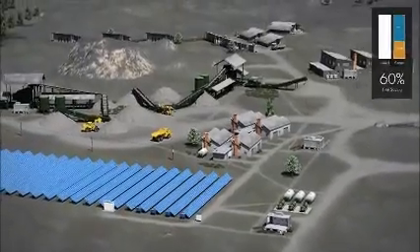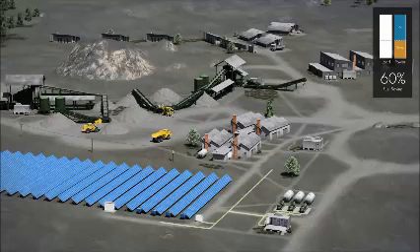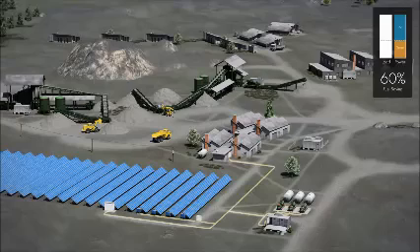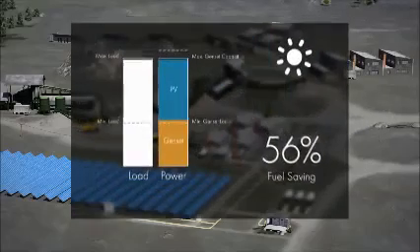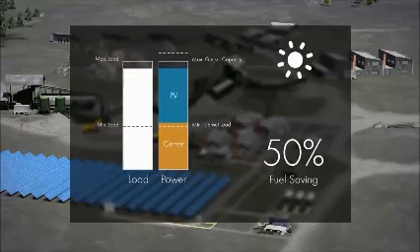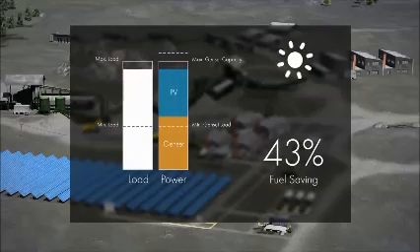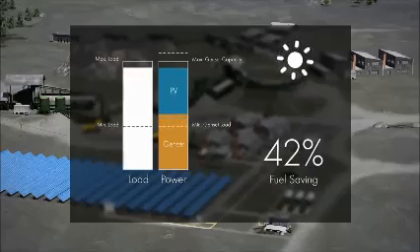The SMA Fuel Save solution automatically synchronizes the PV system with the diesel grid. All information, including grid properties, load requirements, and minimum genset loading, are taken into account when the SMA Fuel Save controller defines the optimal PV power set point. It is extremely important to have a secure and reliable operation at all times. The SMA Fuel Save controller enables the hybrid system to meet any dynamic grid requirements.